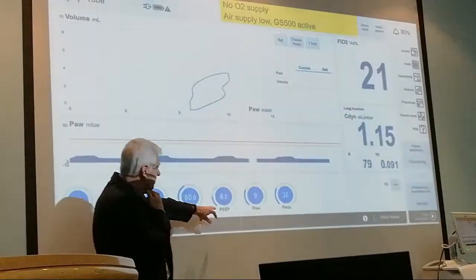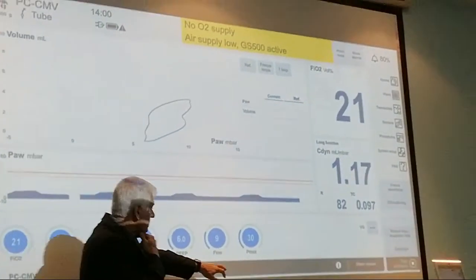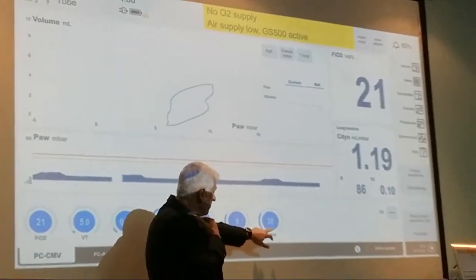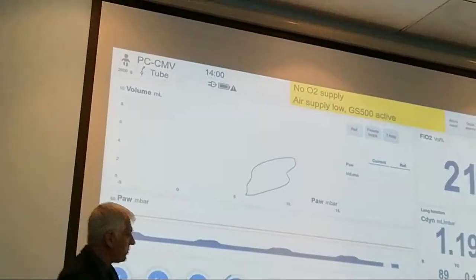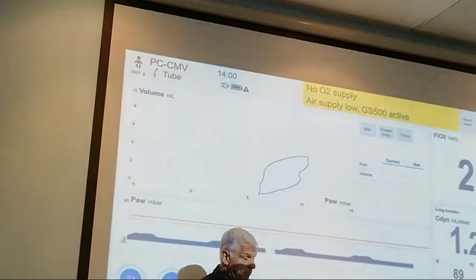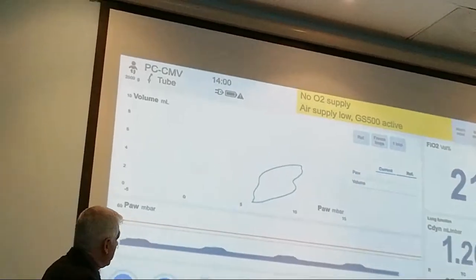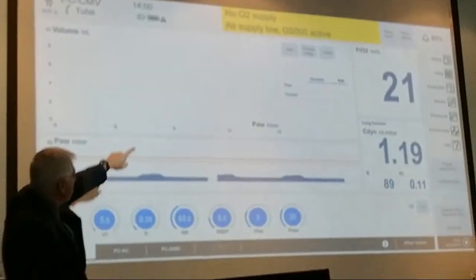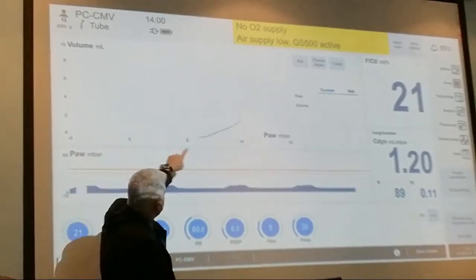PEEP of 6. We put a P max of 30, so the machine will not deliver more pressure than 30. It may not be able to deliver the volume. If your volume is too high and it needs to generate more pressure to get the whole volume, the machine won't allow that and will alarm and tell you that it cannot deliver the volume because your PIP pressure is too low.